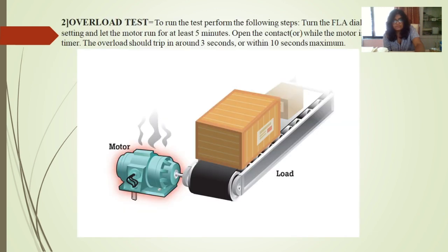An overload test. To run the test, perform the following steps. First, turn the FLA dial back to its proper setting and let the motor run for at least 5 minutes. Open the contact while the motor is running and start a timer. The overload should trip in around 3 seconds or within 10 seconds maximum.